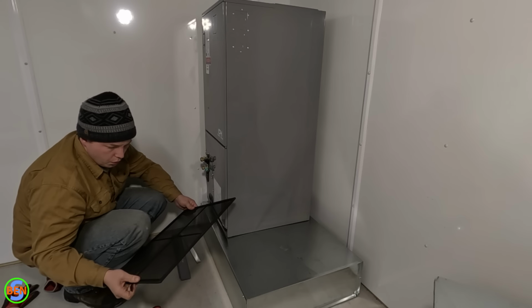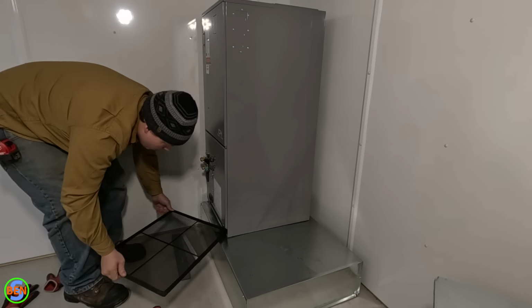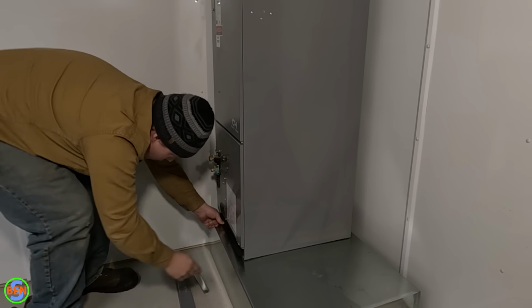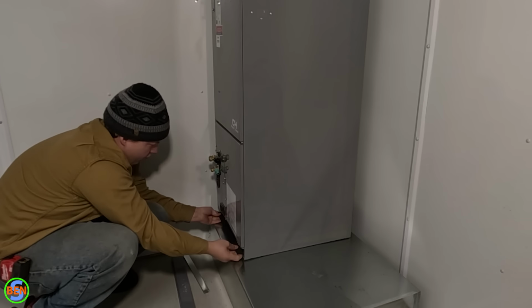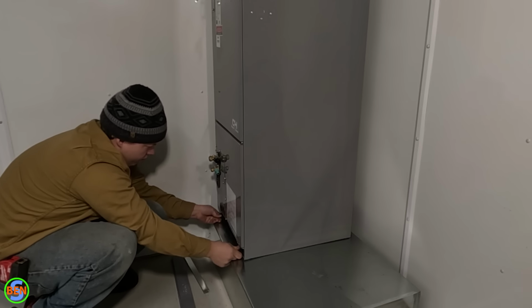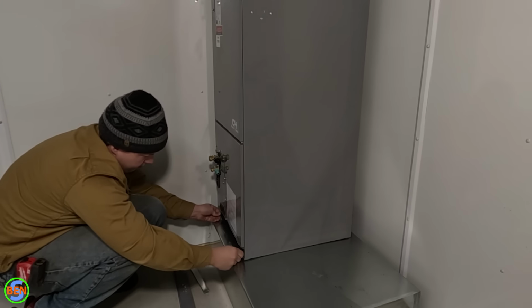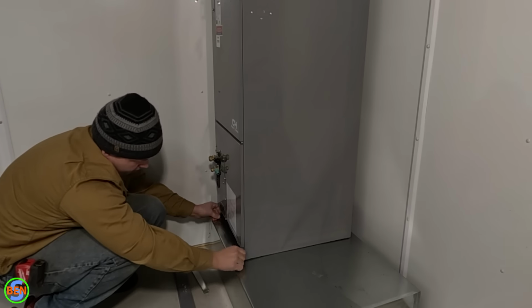A couple other details with the ductwork are that with an air handler unit, you're going to have a dedicated filter. This one is no different in that we have a 16 by 20 filter that is able to be installed on that air handler. My recommendation on air filters is that you should buy the cheapest pleated air filter that you can get your hands on. Don't buy the really expensive ones with a really high MERV rating, like a MERV 12 filter, because it's as if you're putting a plugged filter in right away. If you want a high MERV rating filter, you need to get a filter rack assembly or whatever that is going to be for like the 4-inch filters, the really thick ones, so you can get more surface area so you don't mess up your unit with excess static pressure.